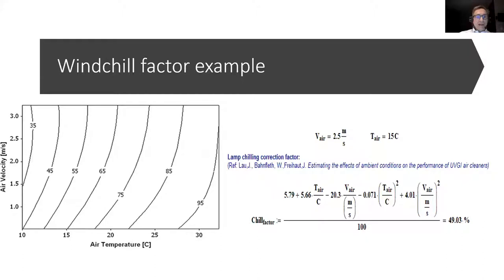So the wind chill factor, an example of air moving at 2.5 meters per second, which is typical in an air handler, temperature of air of 15 degrees Celsius after cooling. Well, with your chill factor, you've lost more than half. What it tells you is do not put a bare lamp in an airflow. It's not a good idea. And that's just for the wind chill factor. Then there's the fouling that will come if your lamp is not shielded properly. So the lamp will foul. And with the chill factor, at the end of the day, a lot of people were disappointed. They said, oh, we tried UV, it didn't work. Well, it was probably misapplied. And it's very tempting to just put a bare lamp and say, it can do the job. Well, practically speaking, no.